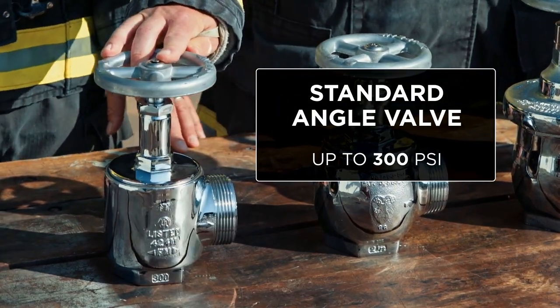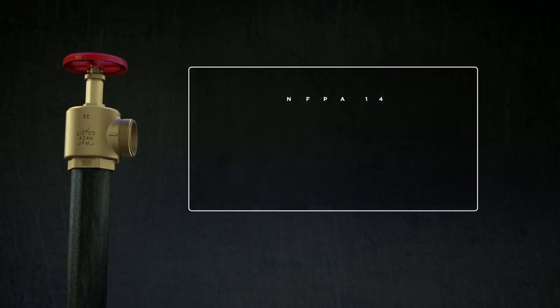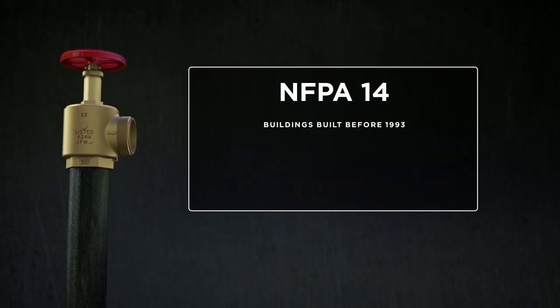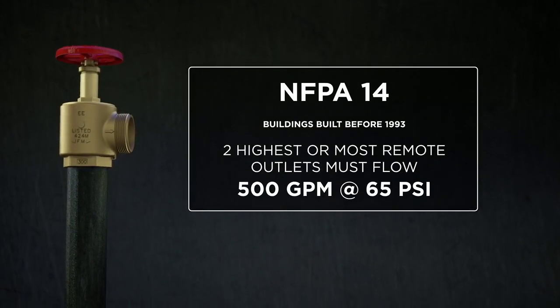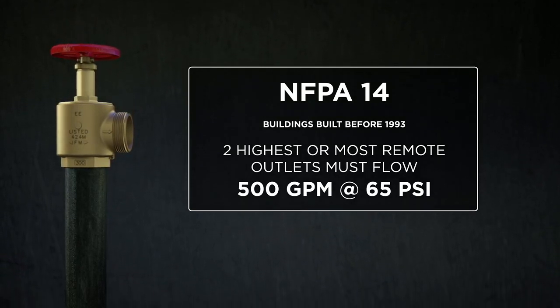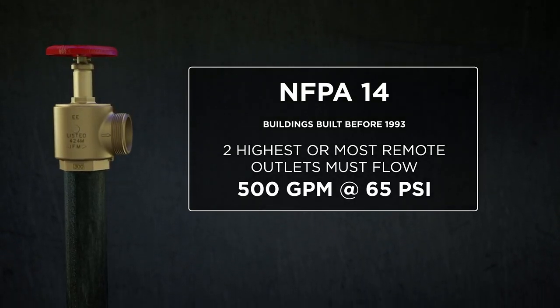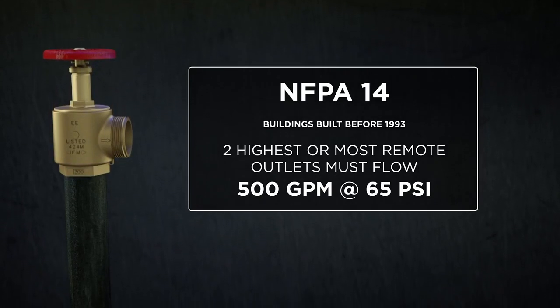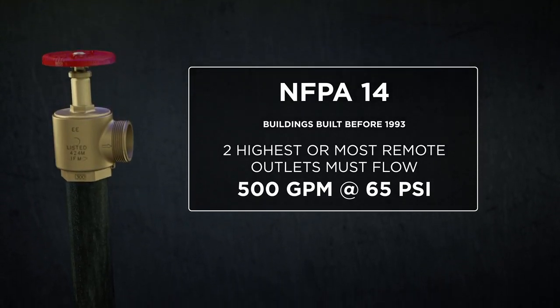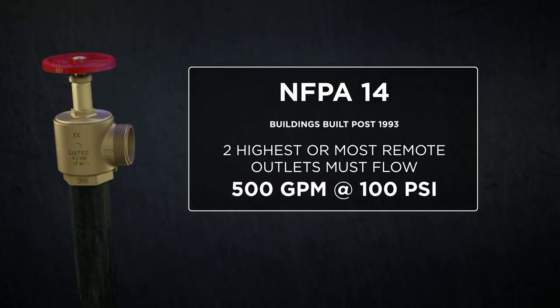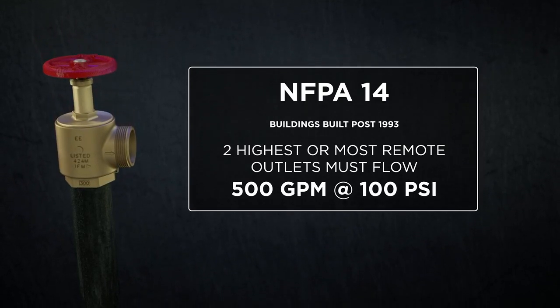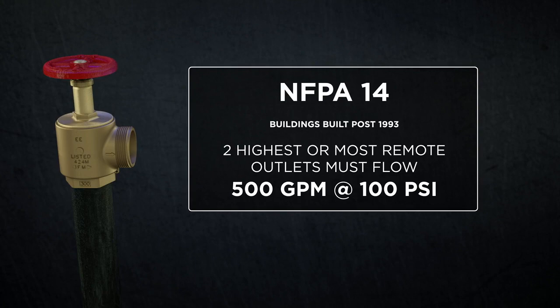Fire code requirements for pressure and flow for standpipe hose valve outlets is driven by NFPA 14. NFPA 14 states that the top 2 outlets or most remote outlets in a building must flow 500 GPM at 65 PSI for buildings built prior to 1993.